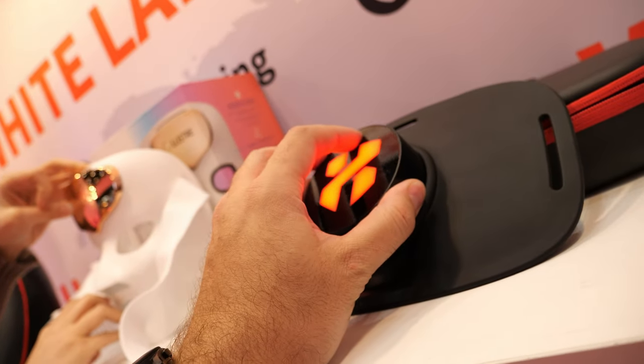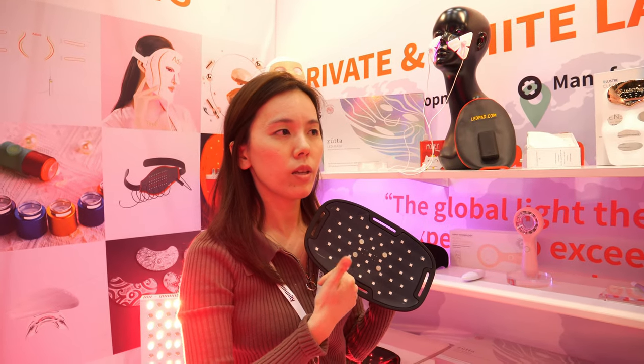What is the frequency of the light — is there a specific wavelength? They have specific wavelengths. On the red light, normally we use 650 nanometers, and we have a spectrum range from 630 to 650. The blue light normally uses 450 nanometers, and infrared is over 800 nanometers.